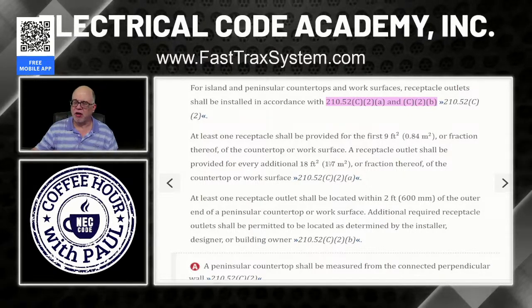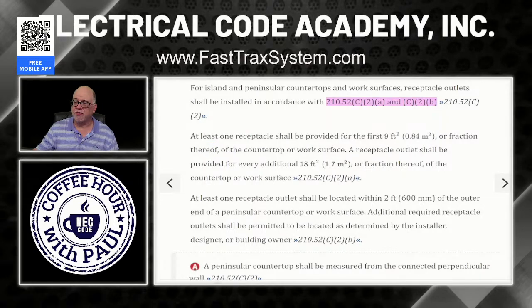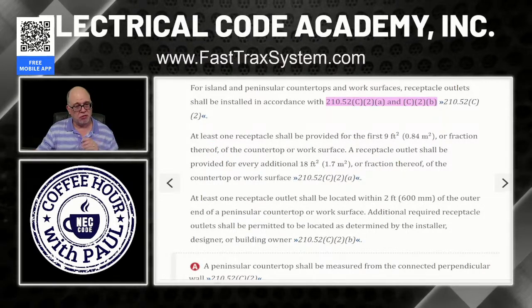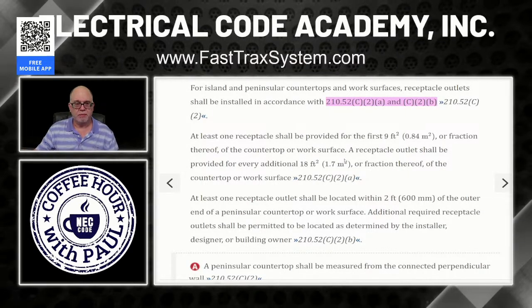All right, so let's start looking at the math here. You have to have at least one receptacle installed for the first 9 square feet, or fraction thereof. And what's a fraction thereof of 9 square feet? 8 square feet, 7, 6, 5, 4 square feet, all of those are fractions thereof of the first 9 square feet, okay? So you have to have at least one, right?